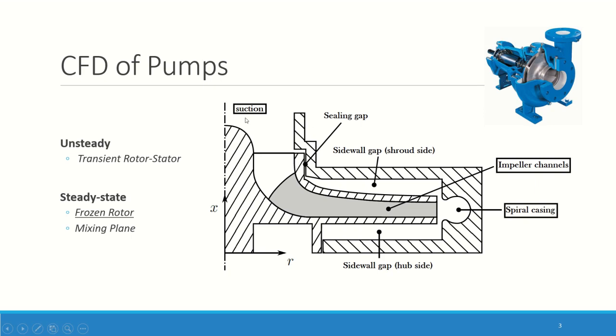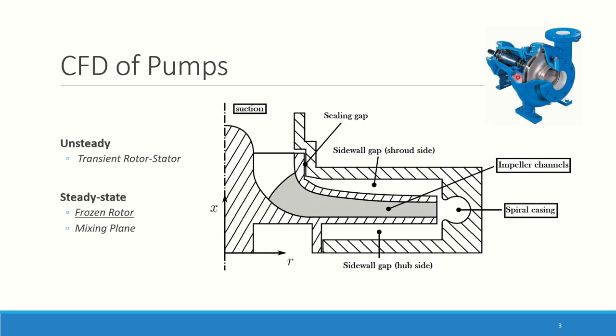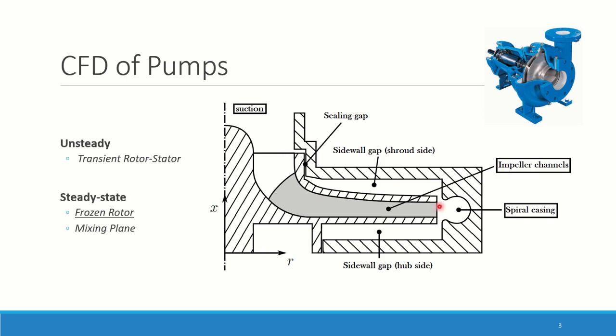To talk about the different parts of the pump. You have first the suction, which is where the water is coming from. The water then goes into the impeller channels, is collected in the spiral casing and goes out to the outlet. Here you can see two sidewall gaps on the shroud and the hub side, but we're going to neglect them. Physically you will have a high pressure region here, a low pressure region here, and recirculation appearing. But in preliminary design or when you want to compare a lot of designs, it's common to completely neglect these sidewall gaps. So we just put walls here for simplifications.